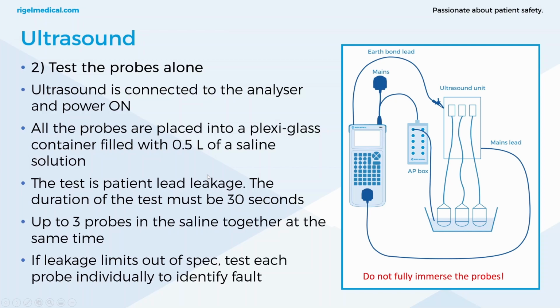In the second part, we test the probes alone. So the ultrasound is connected to the analyzer and powered on. All the probes are placed into a plexiglass container filled with half a litre of saline solution, and you can place up to 3 probes in the saline together at once. We're doing a 30-second test.